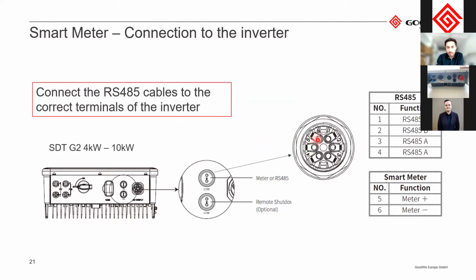Here you see how to connect the upper port. So it looks like you have 6 different connections, and it's a bit tricky to know exactly where they go, but there are actually numbers here on the plastic. They're a bit difficult to see, but they are there. And basically you have the 1, 2, 3, and 4, which is the RS485, either B or A. And then the 5 and 6 is the meter for plus and minus. So yeah, please check that and make sure that you connect it to the correct input.